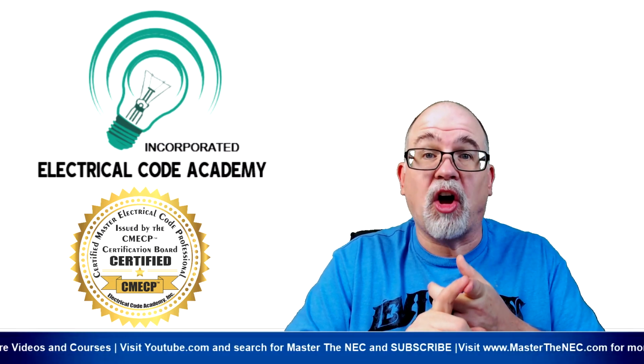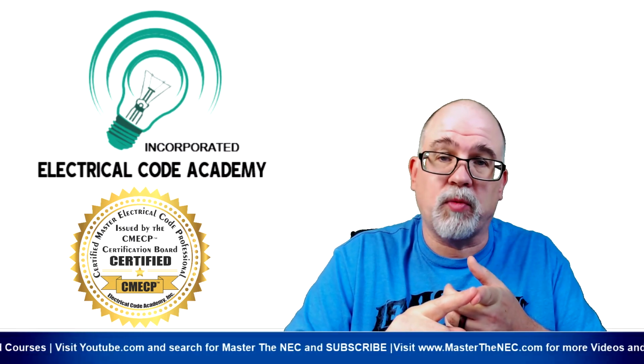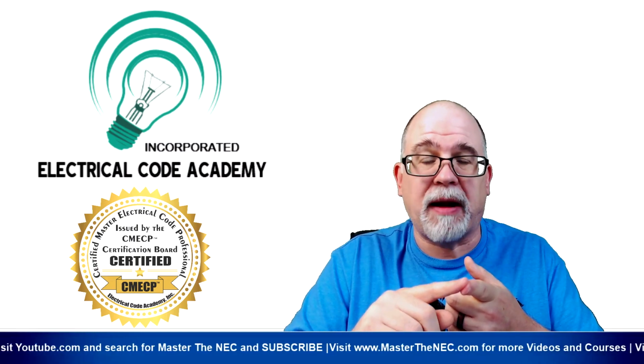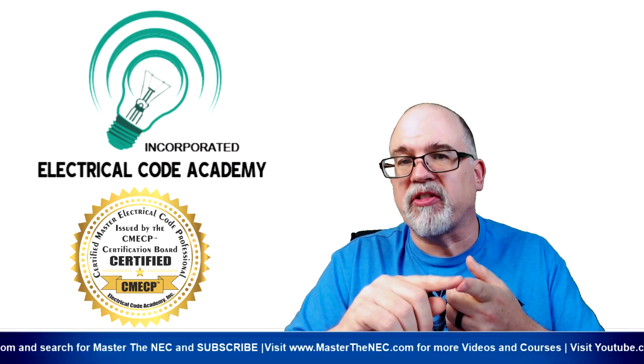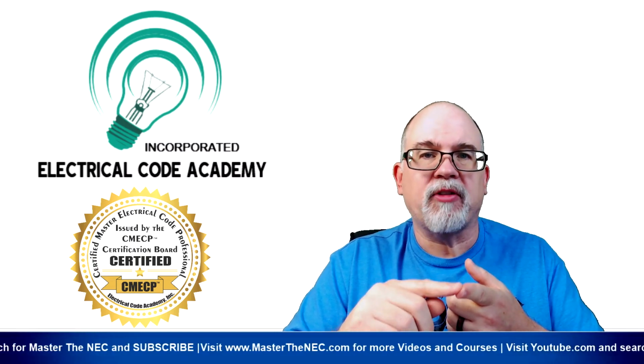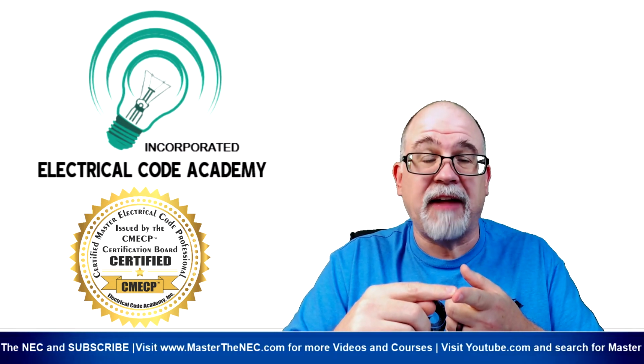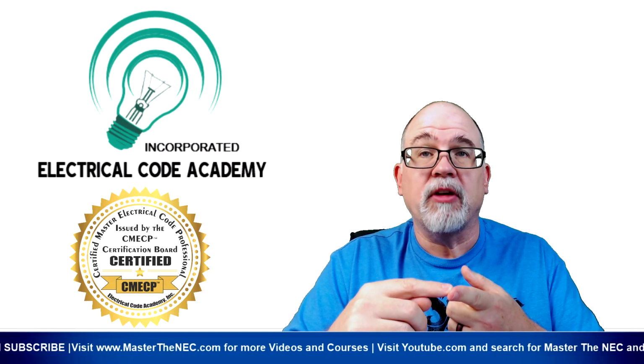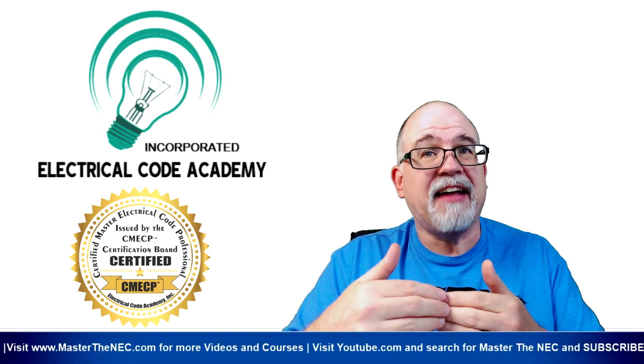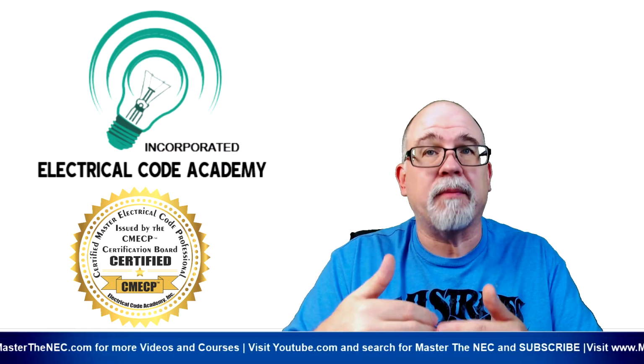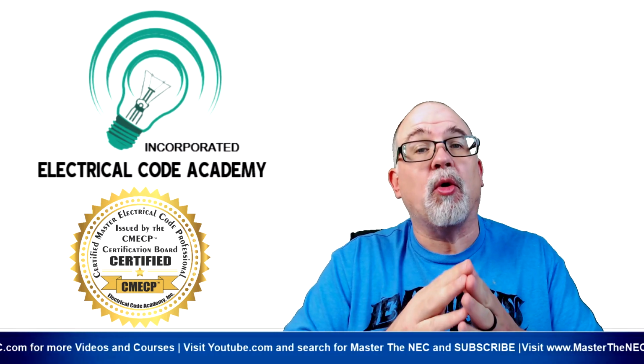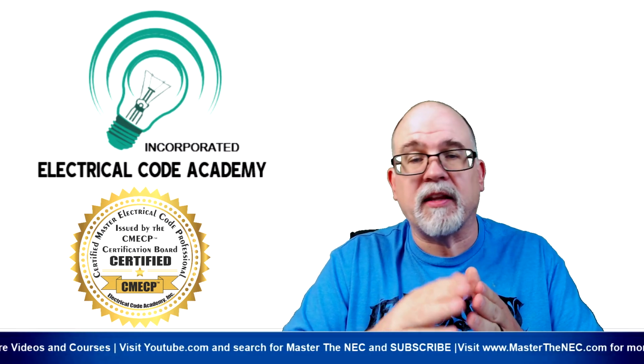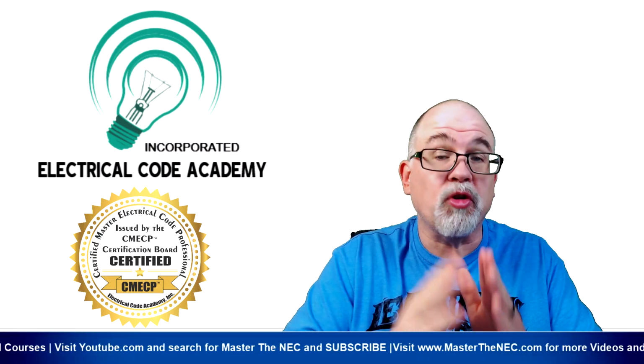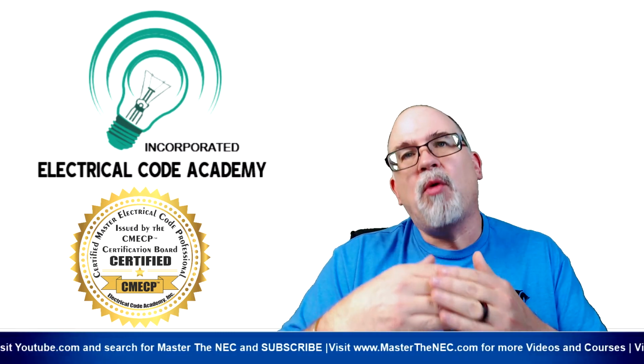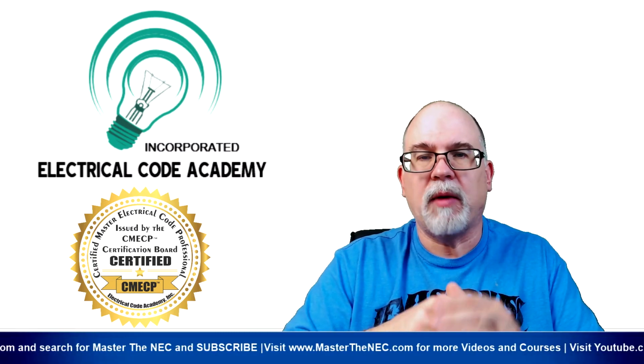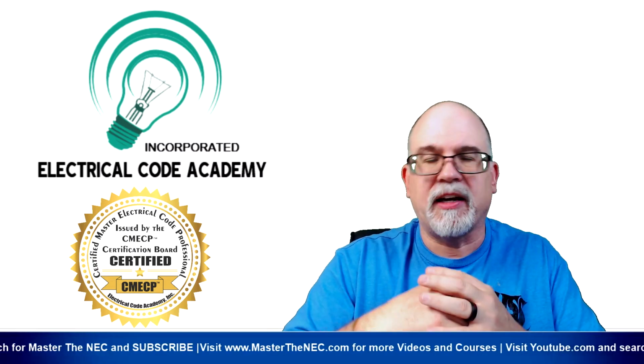And incidentally, it is also protecting our primary conductors as well. Okay, because we took our 90 amp primary rated current and took it at 125%. And that was 112.5 amps. We went to find a conductor that had at least that ampacity rating. We found that we had a 2 gauge that was good for 115 amperes. And yes, since a breaker doesn't correspond, we can protect it with a 125 amp rated device. So that primary overcurrent protection that was protecting the primary is also protecting the primary conductors. So we're good to go there. Okay. Now we're moving on into the secondary conductors, okay? And we're moving away from the tap rules and moving into secondary conductor rules, okay?